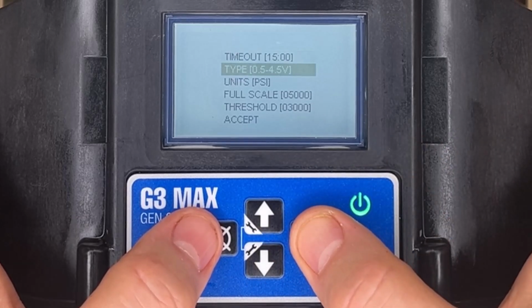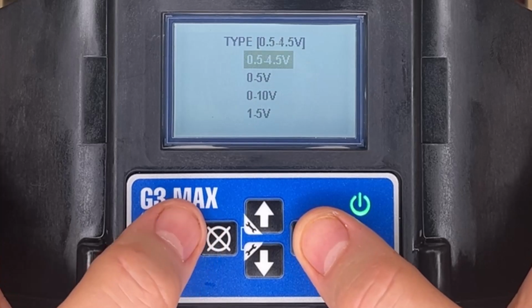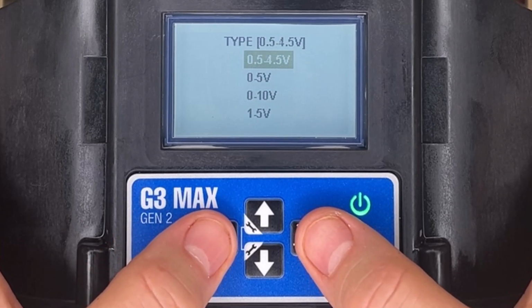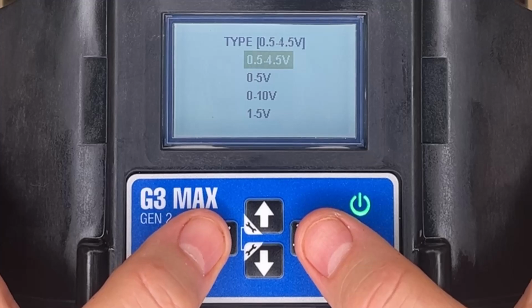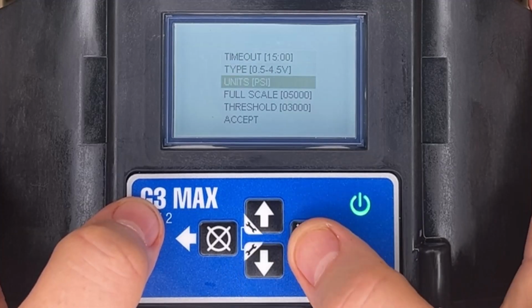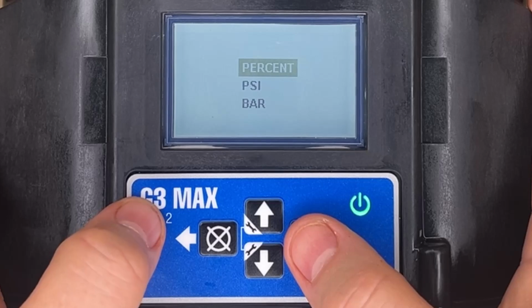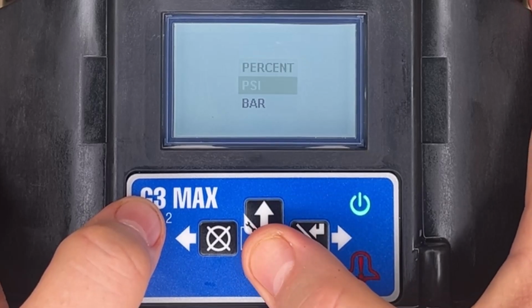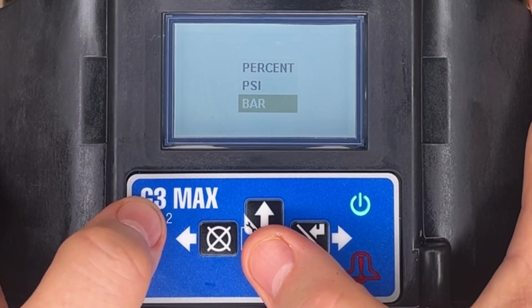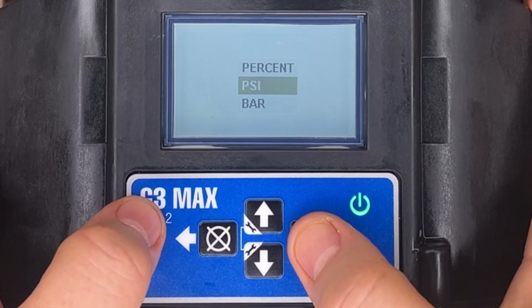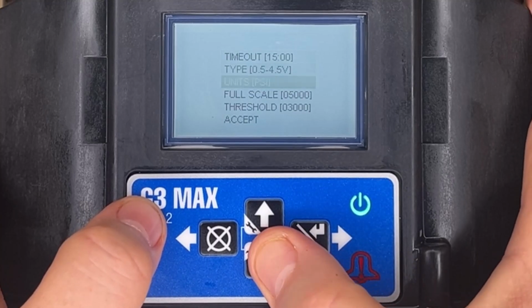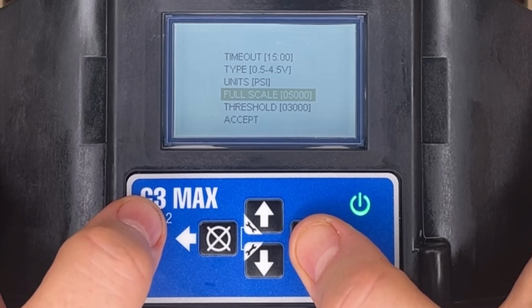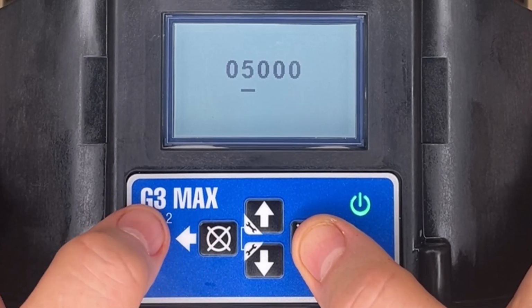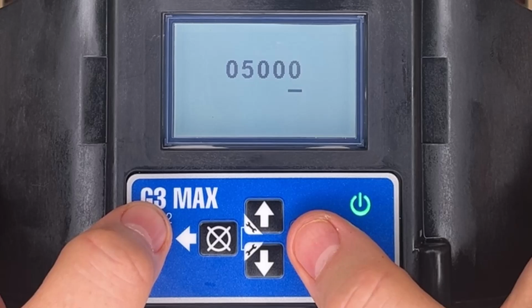You're going to want to look at the packaging or at the product label and see the voltage range of the transducer that you bought. Now the units, you can have this set as either a percentage or PSI or bar. Because I usually use PSI, we're going to go with that. Full scale is another detail that you need to get off the packaging or the product label of the transducer that you purchased, and then just set the number to that.